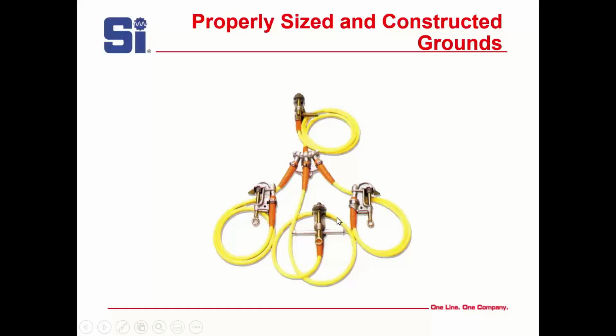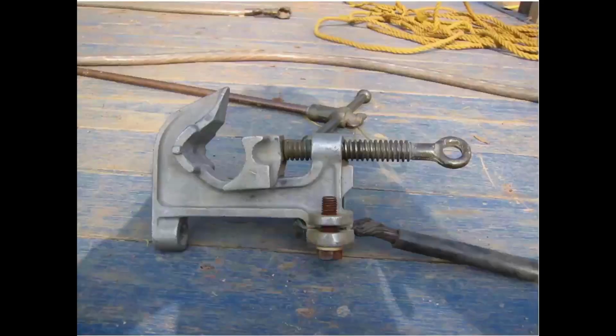Again, this is a good ground. It's got all the right parts. They're all rated. As a matter of fact, at one of the ASTM meetings I went to, for the F855, the manufacturers are saying that a lot of people take components from different manufacturers and assemble them, and they recommended that not happen because the different parts are not designed to go together with each other. And that surprised me. I've never heard that before. But they were pretty stringent about it. And they're not trying to sell ground cables. They do that anyways. Here's a bad ground cable.